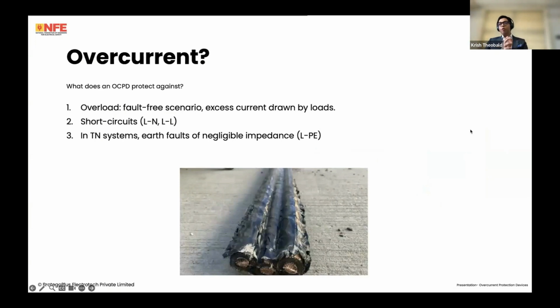So what is an overcurrent and what does an OCPD protect against? There are three basic ideas. An overload, which is a fault-free scenario. There's nothing wrong in the circuit. It's just that there's excess current drawn by loads. For instance, you have a motor that is drawing more current because there is something wrong with the actual load. Or say you have a socket and you have a lot of loads connected, a lot of extension cords, and so on and so forth. That's a fault-free scenario where there's excess current drawn by loads.